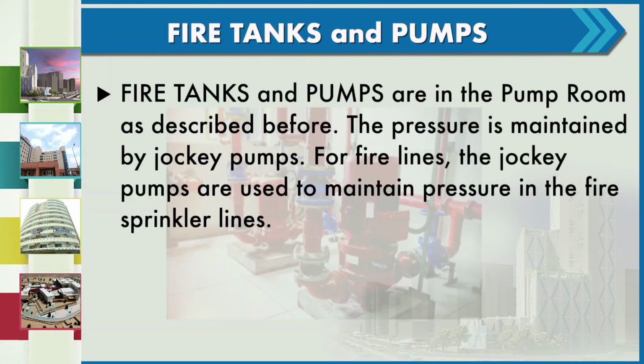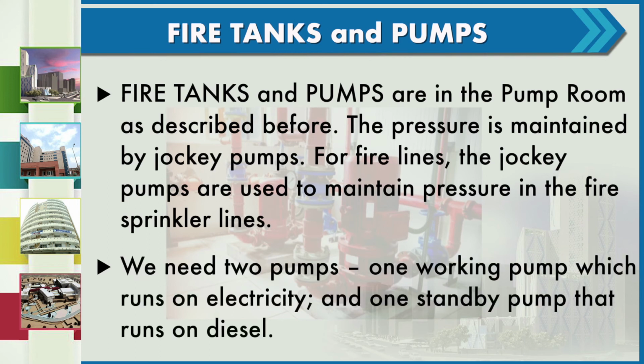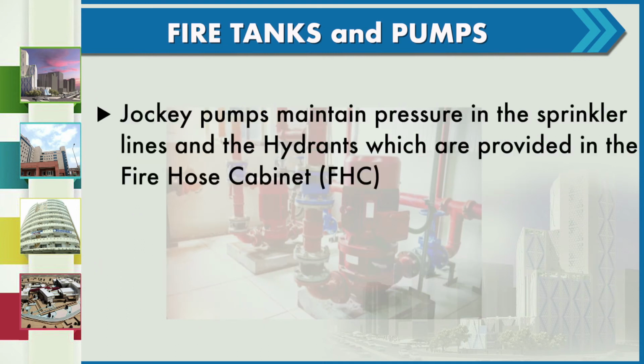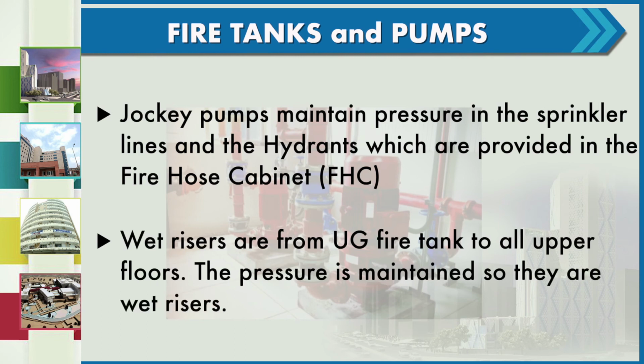Fire tanks and pumps are in the pump room as described before. The pressure is maintained by jockey pumps. For fire lines, the jockey pumps are used to maintain pressure in the fire sprinkler lines. We need 2 pumps, one working pump which runs on electricity and one standby pump that runs on diesel. Jockey pumps maintain pressure in the sprinkler lines and the hydrants, which are provided in the fire hose cabinet. Wet risers are from the underground fire tank to all the upper floors. The pressure is maintained, so they are called wet risers.